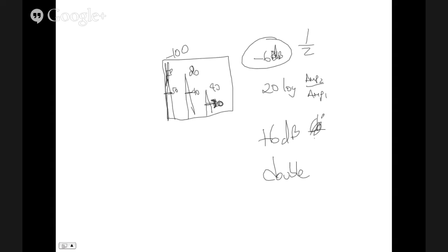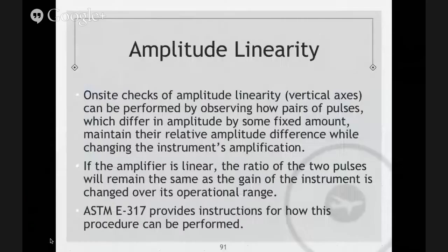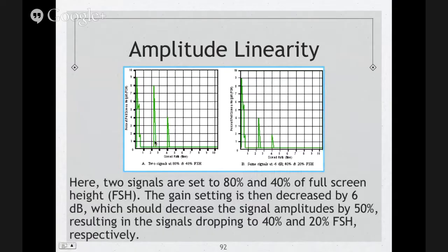That's what they mean by that. That if the amplifier is linear, the amplifier or the volume control, the ratio of two pulses, whether it be echoes or otherwise, will remain the same as the gain instrument is changed over its operational range. You can see it here. Over here by the left, you have your first echo pulled up at 80%, and your second echo pulled up at 40%.